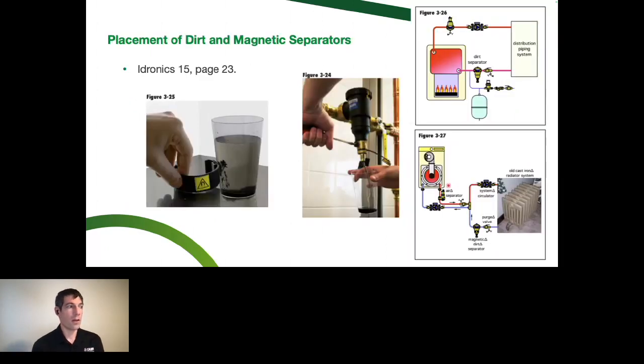How do we know if we need more magnetic separation or if we need to blow down these devices more frequently? You just kind of have to test. So what I would recommend in a commercial system is to get a big white bucket and blow the vessel down into the bucket and see how much of this debris is reactive to a magnet. And then just put that into the schedule that the maintenance person should do that once a week in the most extreme cases. And if after a week in one of these separators you only get just a couple grams of debris, then maybe you only have to do it once every 6 months or once every year when you're doing an annual service or something.